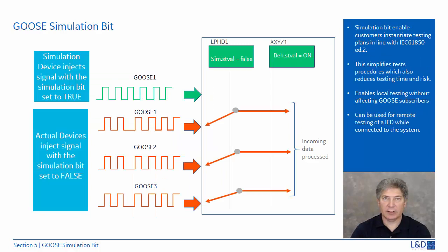Maintenance testing in cases such as IED maloperation requires it to be tested before putting it back in operation. In the typical case, this requires sending a testing crew to the substation to perform the testing, a time-consuming and very expensive process. The use of protection systems in a digital substation environment allows the testing to be performed remotely. However, the use of both sampled values and GOOSE messages is required for the end-to-end testing.